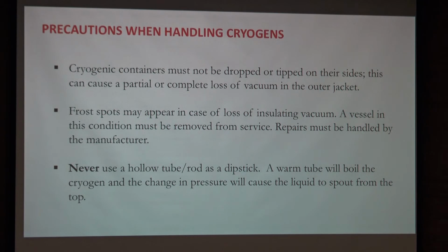Either you can evacuate your dewar yourself, or in some cases it may be necessary to send it back to the manufacturer and have them fix it. But if you notice that the outside of the dewar starts to frost up in some spots, then the dewar is probably no longer safe to use. That's the general knowledge.